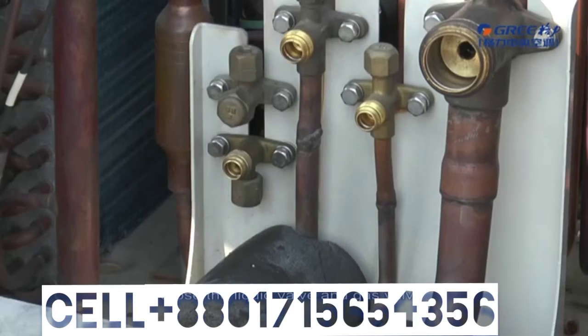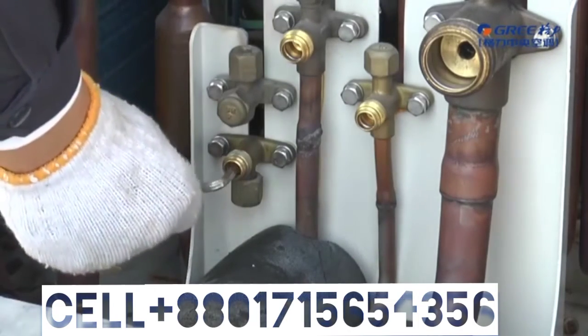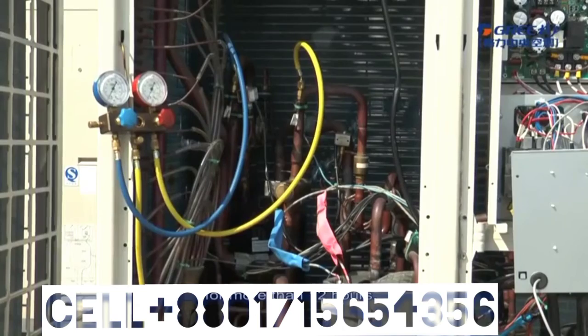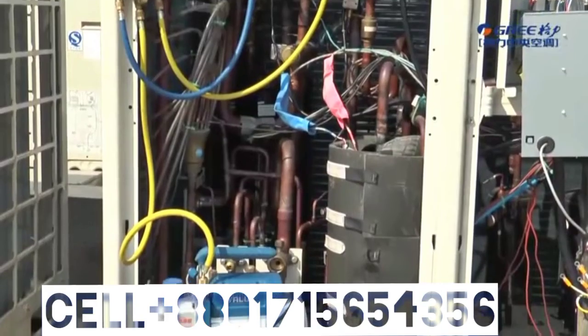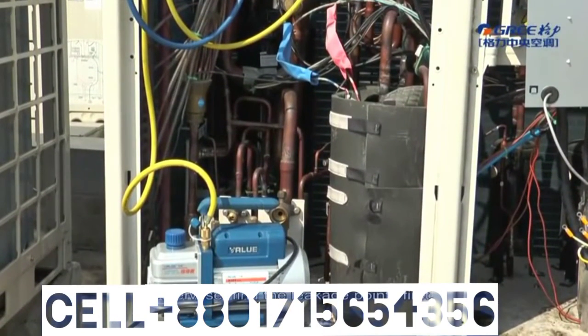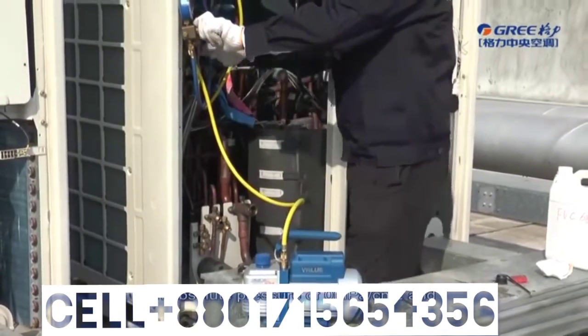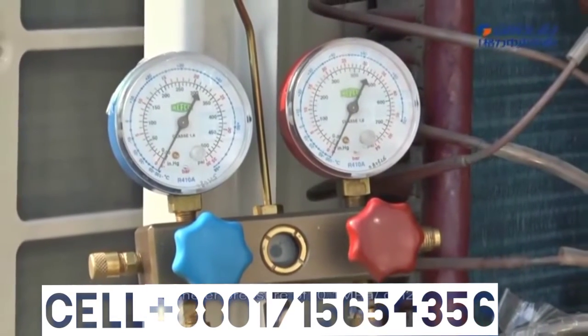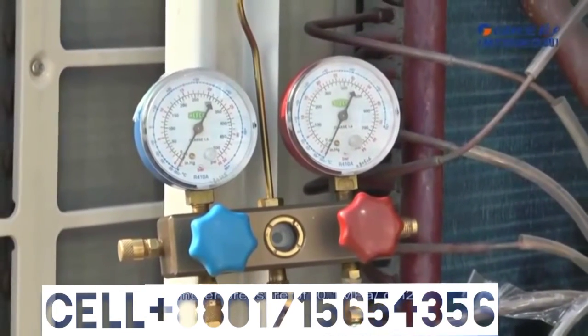3. Finally, charge nitrogen into the system again for pressure check. Close the liquid valve and the gas valve and keep the system pressure up to 2.5 MPa for more than 12 hours. If the pressure remains unchanged, you can arrange vacuuming. Otherwise, find the leakage point first. Make sure the vacuum degree reaches an absolute pressure of 0 MPa per square centimeter and a meter pressure of minus 0.1 MPa per square centimeter.